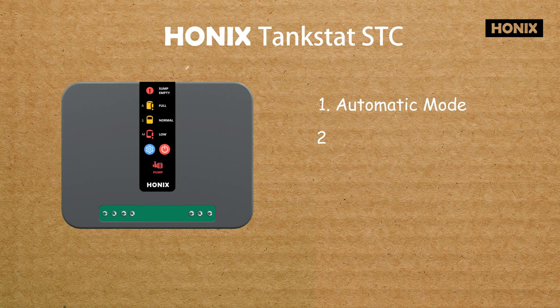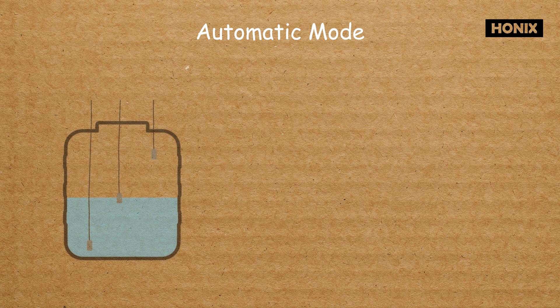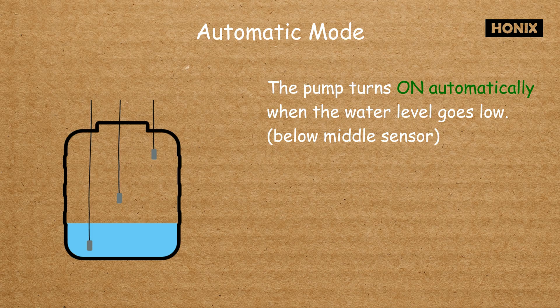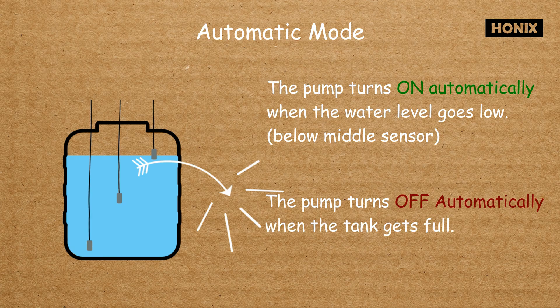In this video we will explore the working modes of the HONIX Tankstat STC water level controller. In automatic mode, when the water level drops below the middle sensor, the pump starts automatically and begins filling the tank. Once the tank is full, the pump switches off automatically.